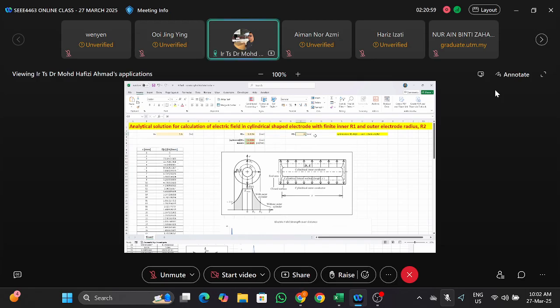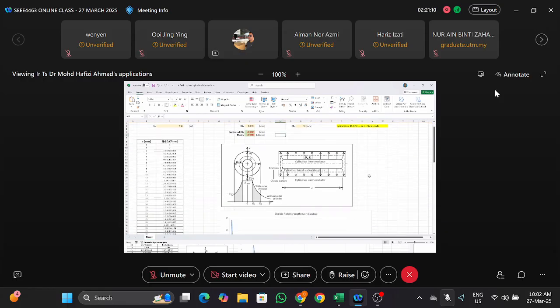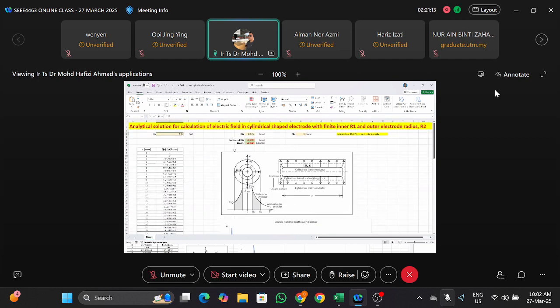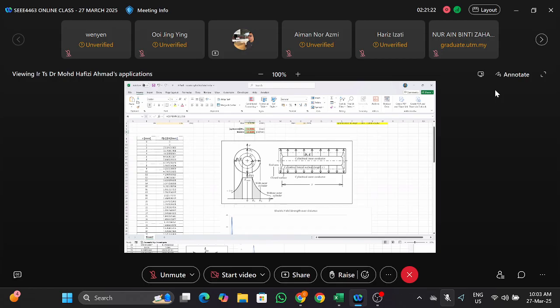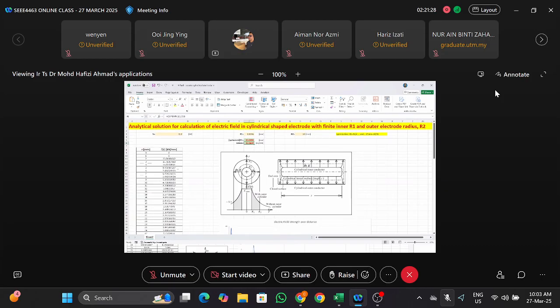So to use a higher voltage with a bigger system, R1 should equal R2 divided by the exponent. But at a higher voltage of 132 kV, the minimum ever electric field will be about 11.9 or 12 kV per millimeter at the surface of R1, the inner electrode. Because of this 12 kV per millimeter at a voltage of 132 kV, we cannot use gas, since it exceeds 9 kV per millimeter.